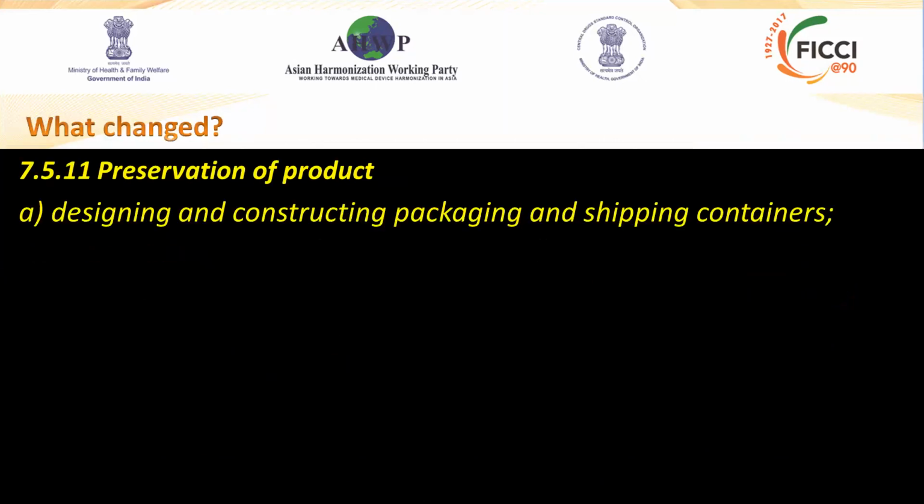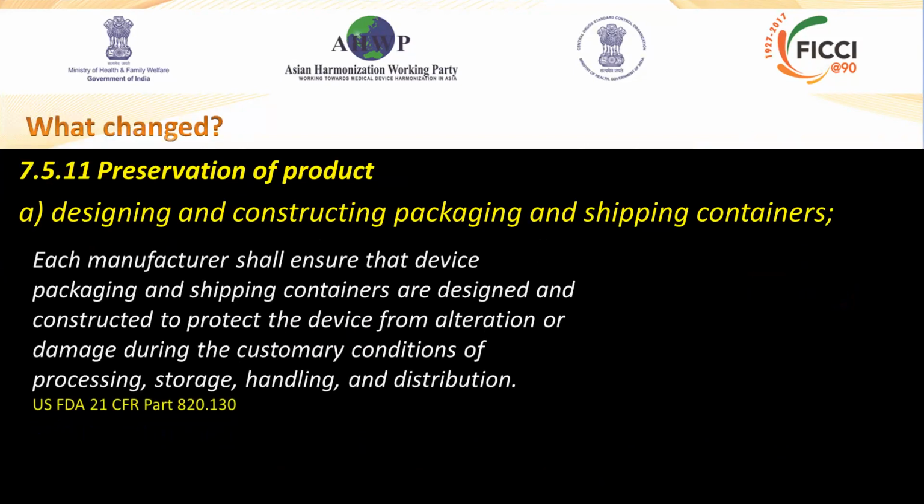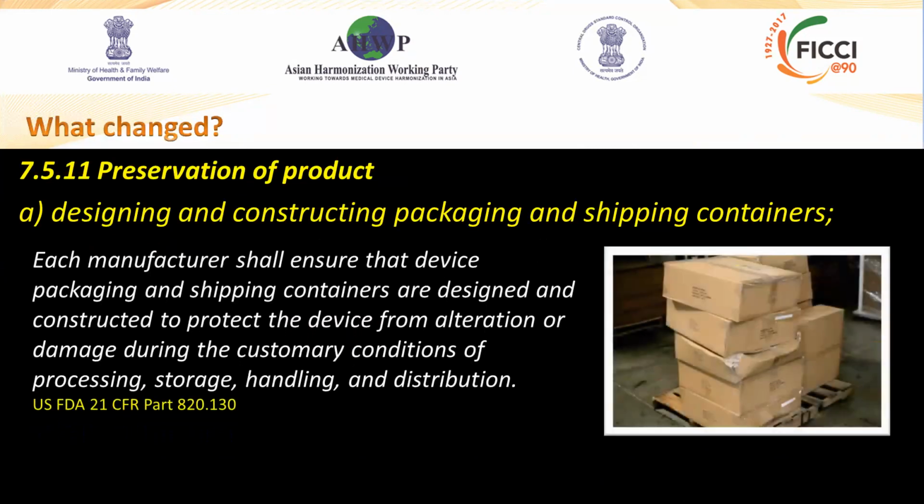Preservation of product, designing and constructing packaging and shipping containers. Each manufacturer shall ensure that the device's packaging and shipping containers are designed and constructed to protect the device from alteration or damage during customary conditions of processing, storage, handling, distribution. This really hasn't changed substantially.